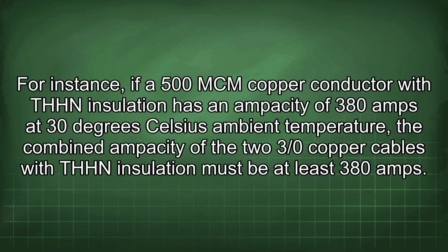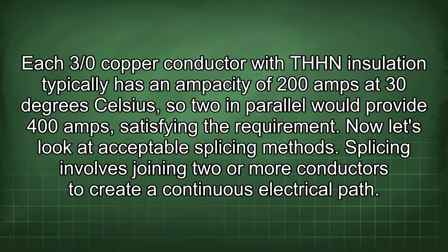For instance, if a 500 MCM copper conductor with THHN insulation has an ampacity of 380 amps at 30 degrees Celsius ambient temperature, the combined ampacity of the two 3/0 copper cables with THHN insulation must be at least 380 amps. Each 3/0 copper conductor with THHN insulation typically has an ampacity of 200 amps at 30 degrees Celsius, so two in parallel would provide 400 amps, satisfying the requirement.